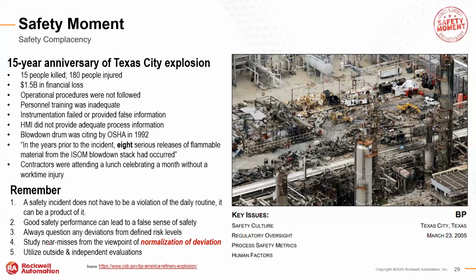So in this case, like I said, the personnel was not trained. The HMI didn't adequately show the process information that it was supposed to. The supervisor actually left the site to go deal with a personal issue, and left a junior operator in charge.